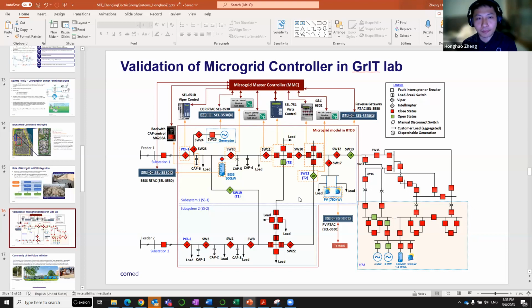Finally, this vendor did not provide us this functionality. For this BESS, we have LG Chem BESS, and we also have an EPC inverter. But that inverter's grid forming capability was only developed maybe several years after we procured this BESS, which means we're already past the time window and cannot do the retrofit anymore. That would give us a headache on the maintenance contract and the relevant business side. So this is more a combination issue of business and technical together.